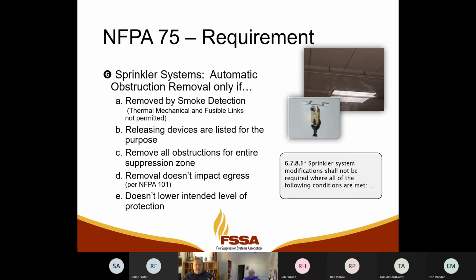You know, what that is leading to is some of the manufacturers are meeting this by using electronic thermal links, and it's a fusible link that can be activated either by heat or a little bit of electrical current, and the electrical current causes a chemical heater to start activating, and it warms the device up and breaks the connection, allows that to fall down. And so those are the devices that they're using. But as they fall down, then there's typically cables that keep that aluminum channel from falling all the way to the ground. And usually they're 18 inches high, because that's the obstruction rule, is that items within 18 inches of the sprinkler are an obstruction. So most of those cables are 18 inches long to allow this to fall down 18 inches and stop.